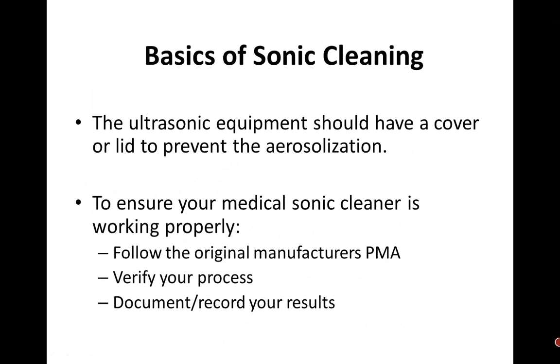You must verify your process. You must trust, but verify. You must document your reports and your results, and then you have something to go back on. Again, if you're asked to show them, that's very, very important. But again, have that preventive maintenance contract with qualified people. Make sure whoever you're using has been trained to repair that. And just because they might know how to use one unit, they should be trained on your unit as well.